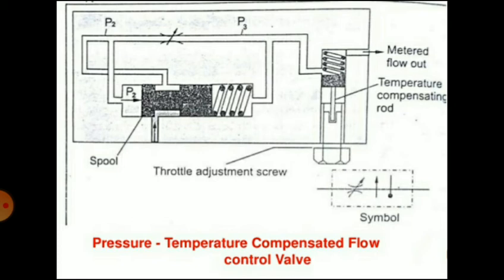The flow from the pressure compensator passes through the temperature compensator, which consists of a spool held against a special alloy temperature compensating rod by a spring. A throttle adjustment screw is provided to adjust the spool setting. As the temperature of the fluid increases, resulting in a decrease in viscosity, this results in an increase in oil velocity and hence increased flow. As the compensator rod is heated due to temperature rise, it expands proportionally to the temperature rise, causing the spool to move against the spring, closing the throttle, and thus reducing the cross-sectional area of flow in proportion to the velocity rise.